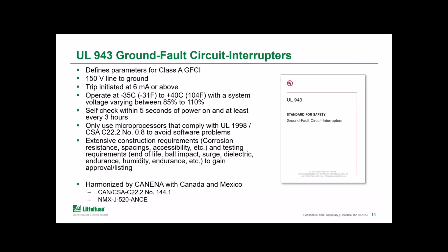This standard for Class A GFCIs is intended for products used on systems up to 150 volts line to ground with a trip level of 6 milliamps of ground fault current. And the trip time is based on an inverse time curve that's specified in the standard. There are many other requirements, and I probably put too many words on this slide, but suffice it to say that this standard requires the GFCIs to go through temperature and humidity cycles, undergo pretty severe physical and electrical testing, and make sure the device has functions like a self-check. So although products or other devices may claim they can trip at 6 milliamps, if it's not listed or approved to one of these standards shown here, you can't be sure it meets all those same requirements.